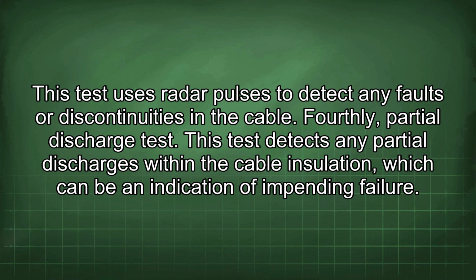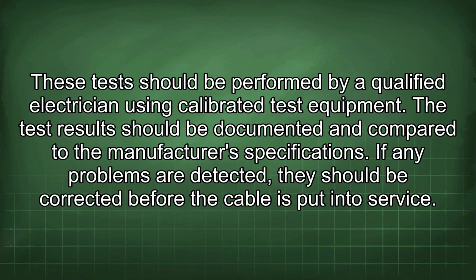Fourthly, partial discharge test. This test detects any partial discharges within the cable insulation, which can be an indication of impending failure. These tests should be performed by a qualified electrician using calibrated test equipment. The test results should be documented and compared to the manufacturer's specifications. If any problems are detected, they should be corrected before the cable is put into service.